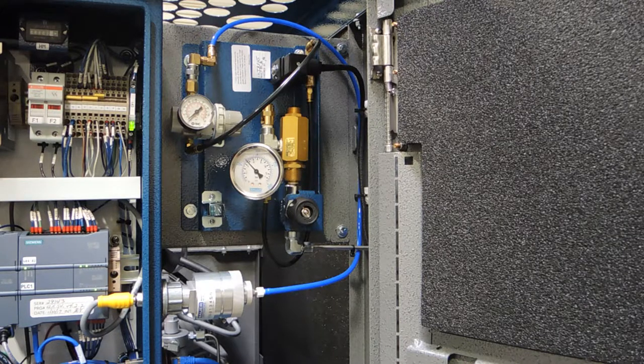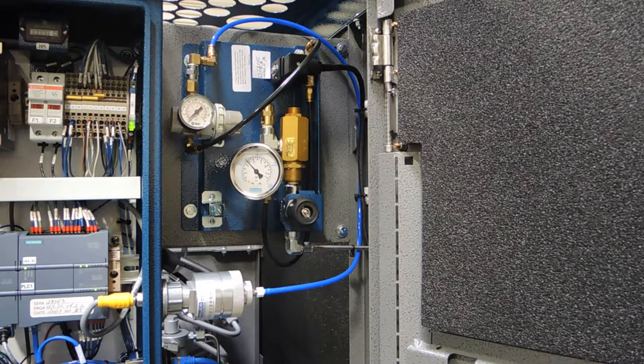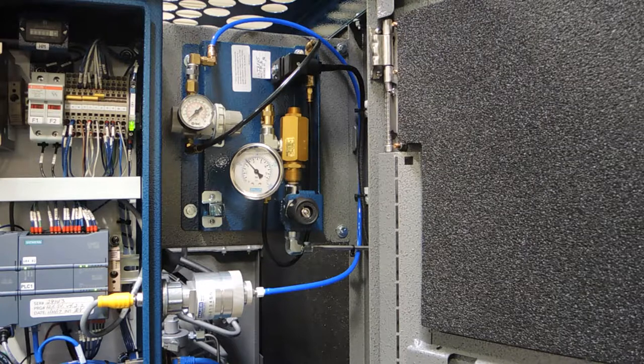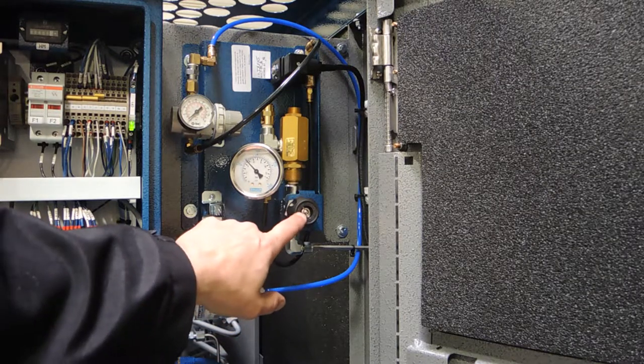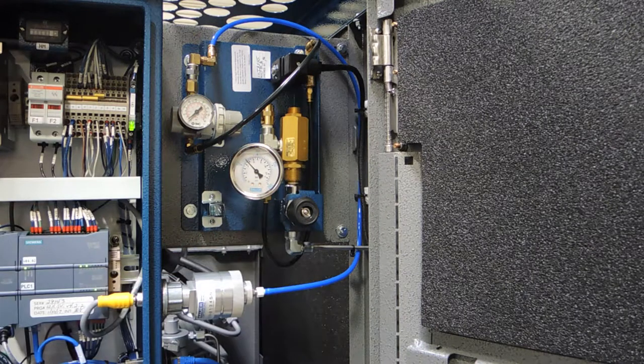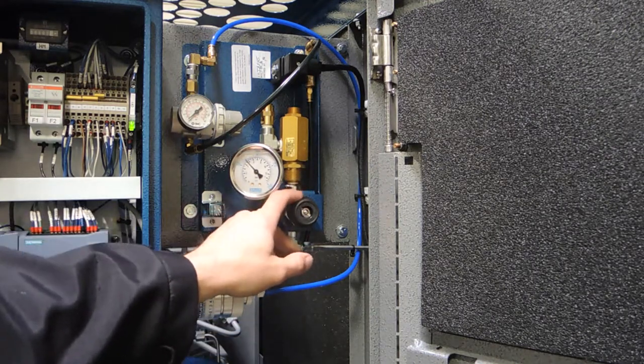This is the CO monitoring system. It's located on the right side of the Unicus 3 and connected to the electrical control panel. I'm going to just point out a few things. This is your valve that controls the high pressure air coming into the system, pulling the sample from after purification. I want to make sure this valve is always left open.